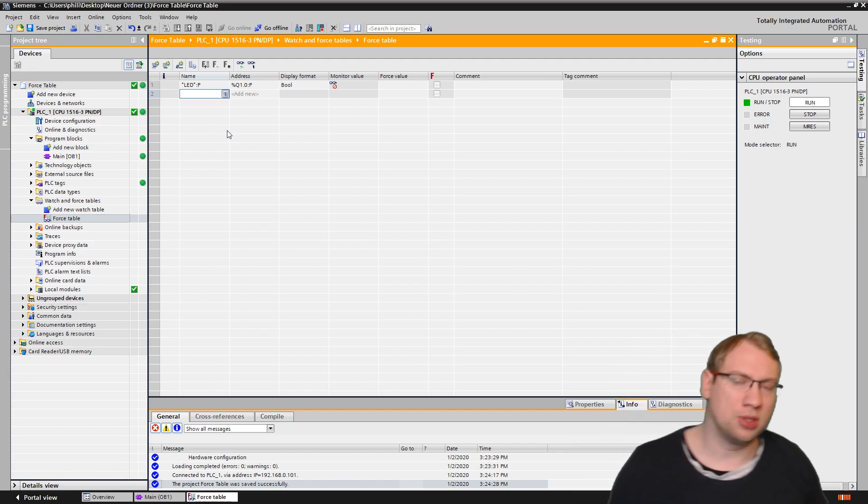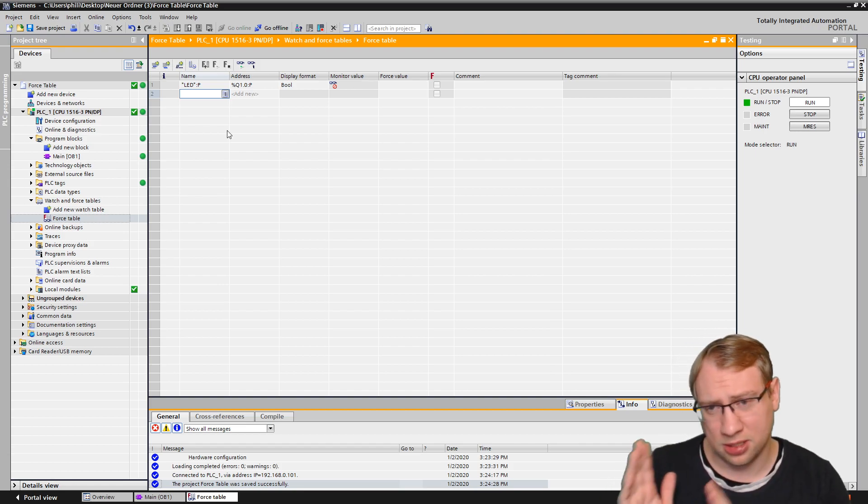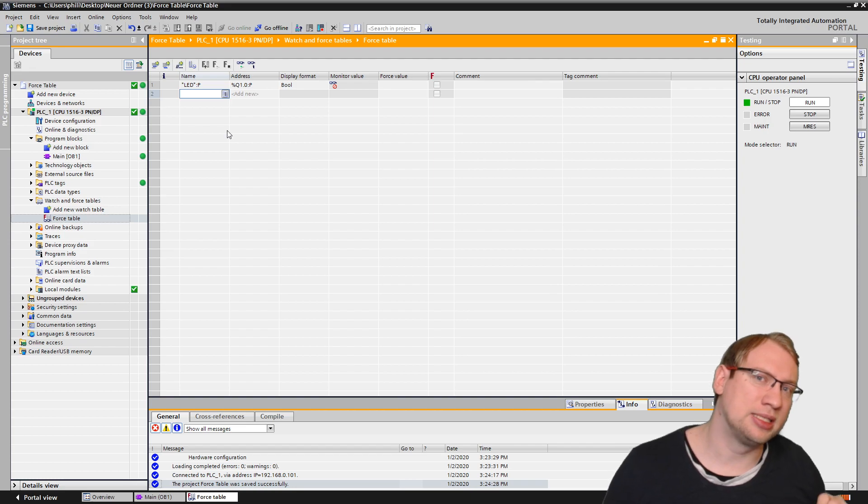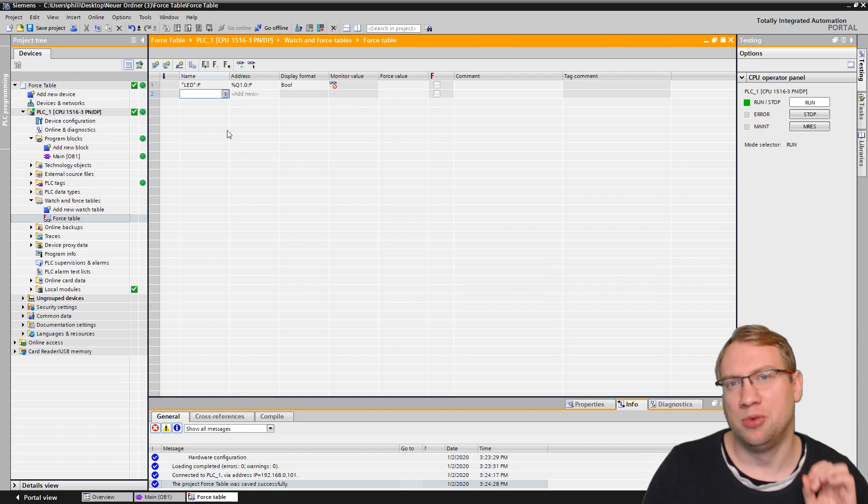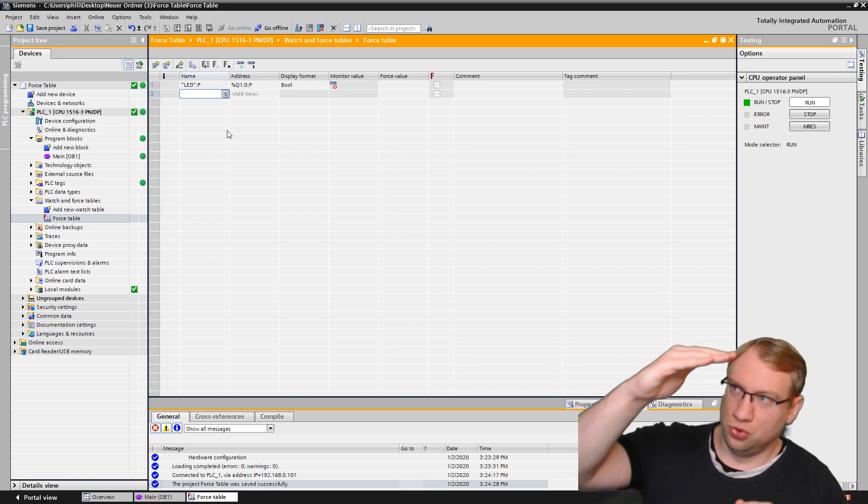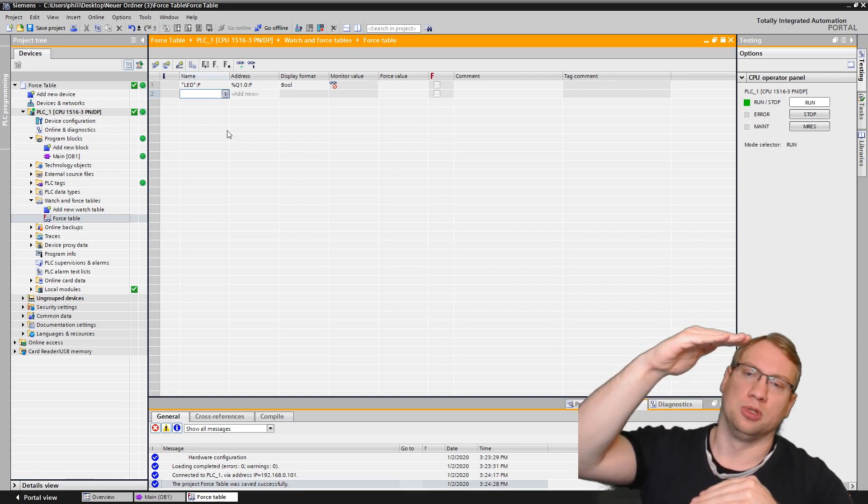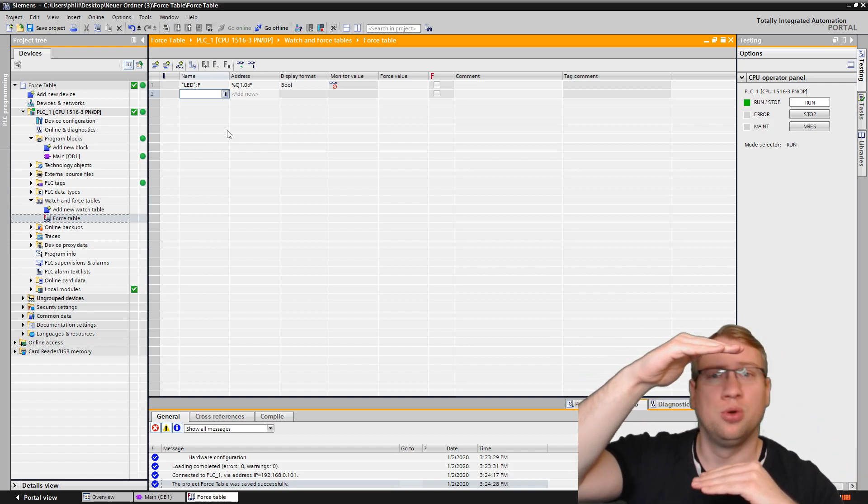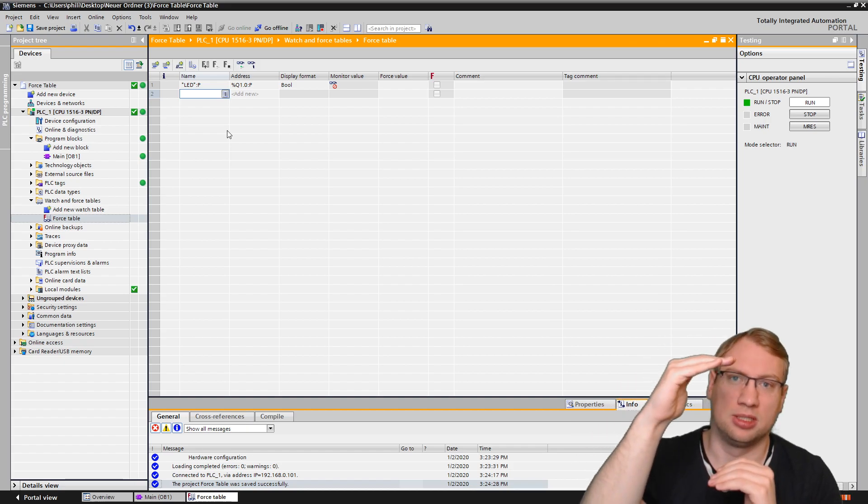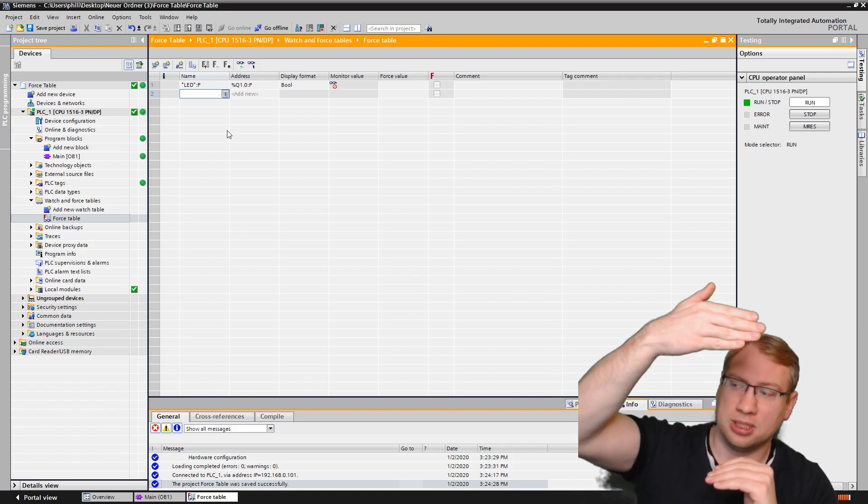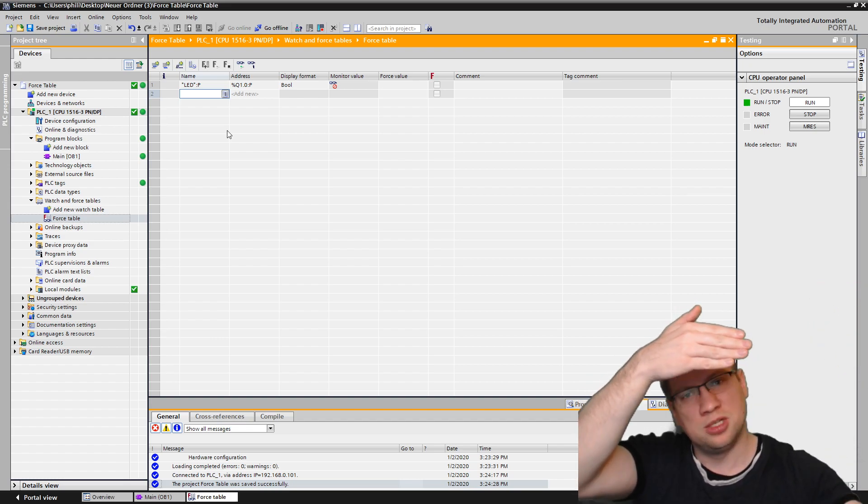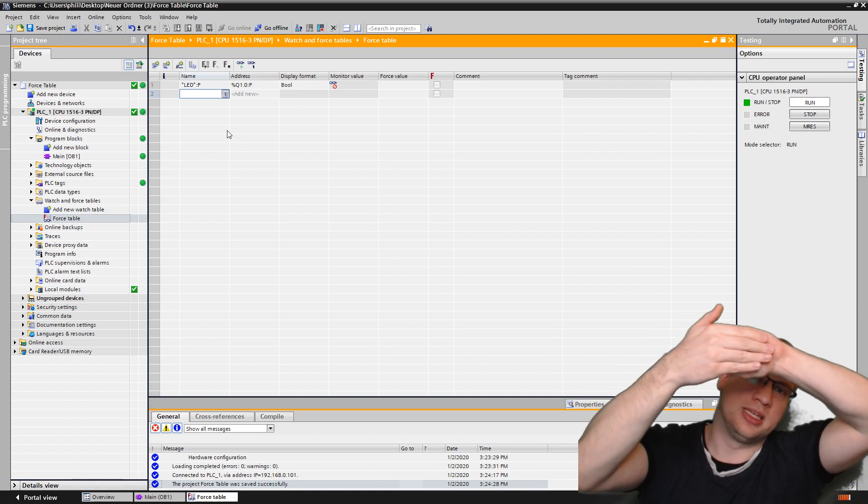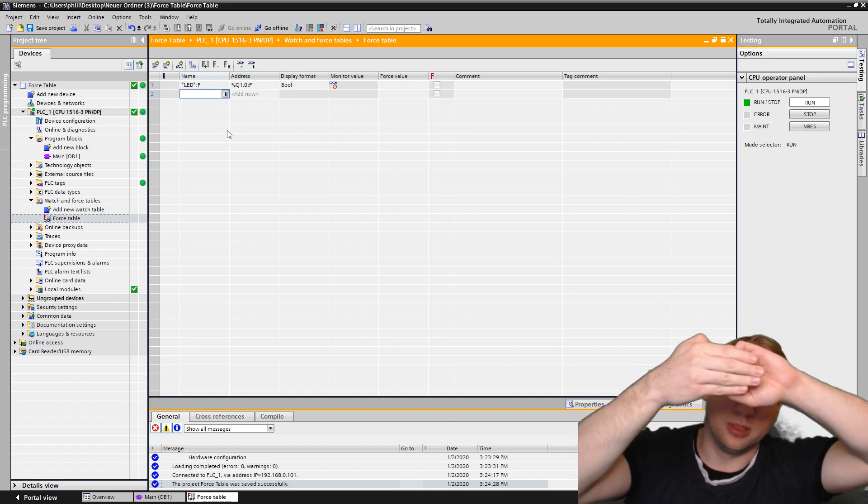This is because our force table, talking about force tables, not about watch tables, directly accesses the PLC peripherals, P, the peripheral input, peripheral output. Meaning, it goes, you're reading your inputs, then you have your program, and then you're writing your outputs. During the program, so in between, you are working not with the peripherals, you are actually working with the tags, with the symbols, with the variables. At the beginning of the program, what happens here, right on the top, is it goes from the peripherals, so from the hardware side, 24 volts, gets transferred and is put into the tag table. So in the beginning, we're translating from the peripherals into tags, into variables.